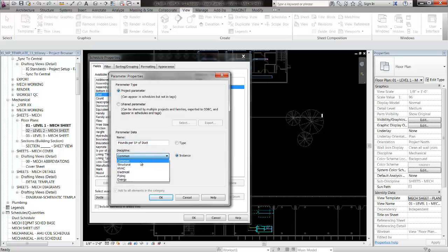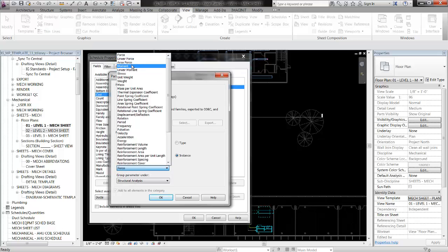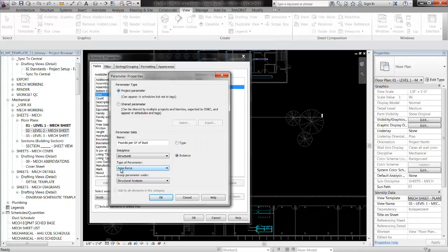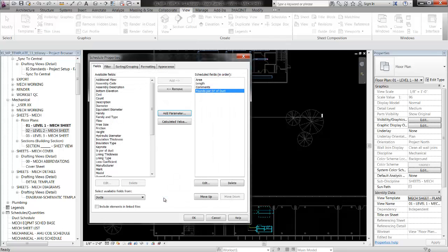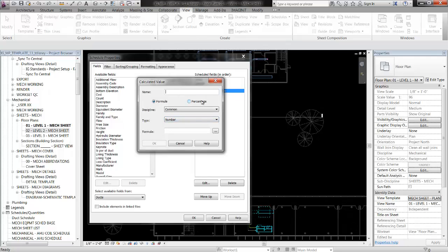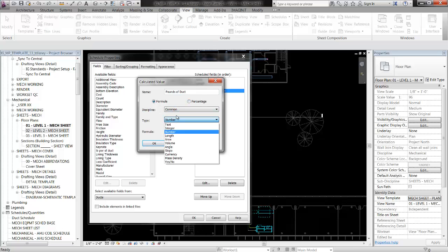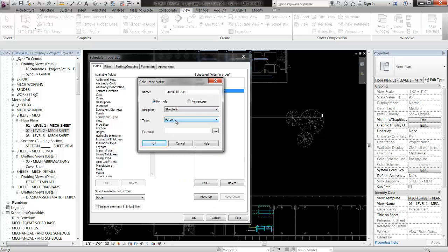We have 'pounds per square foot of duct.' The discipline we're going to make structural, and the type of parameter under area force, so that's going to be pounds per square foot. Let's group the parameter under mechanical and make it a type parameter so we don't have to enter it in for each piece of duct. Hit OK, and then we're going to need to calculate a value — we're going to call that 'pounds of duct,' and it needs to be a force, so that's pounds, and then we get to enter in the formula.